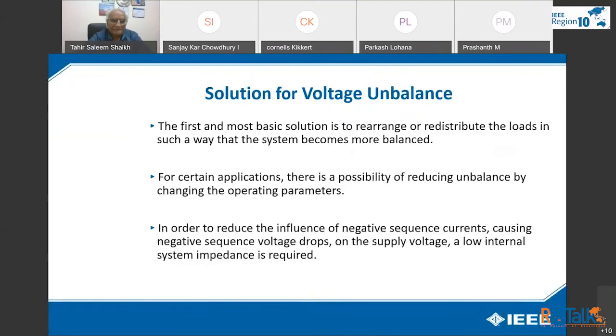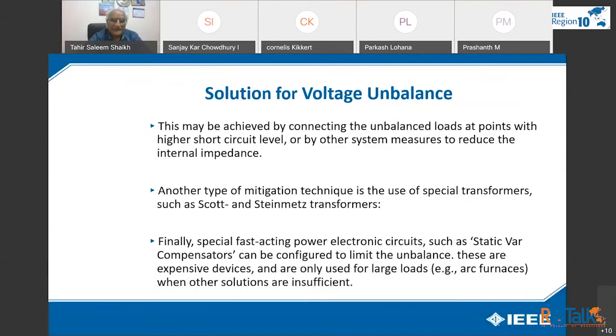The first and most basic solution is to rearrange and redistribute the loads in such a way that the system becomes more balanced. For certain applications, there is a possibility of reducing unbalance by changing the operation parameters. This you can do yourself. In order to reduce the influence of the negative sequence currents causing negative sequence voltage on the supply voltage, low internal system impedance is required. This may be achieved by connecting the unbalanced loads at a point with a higher short circuit level, or by other system measures to reduce the internal impedance.